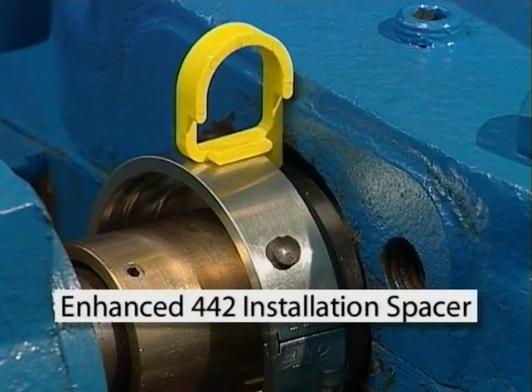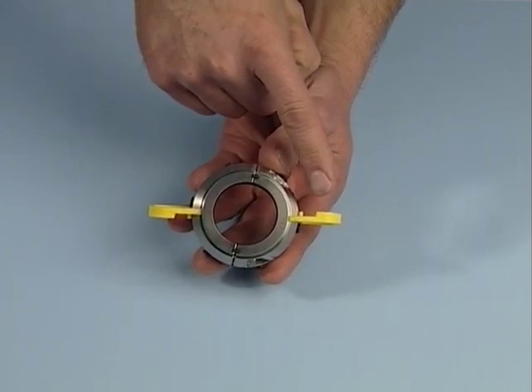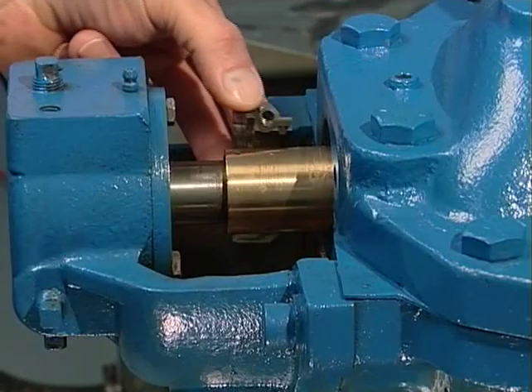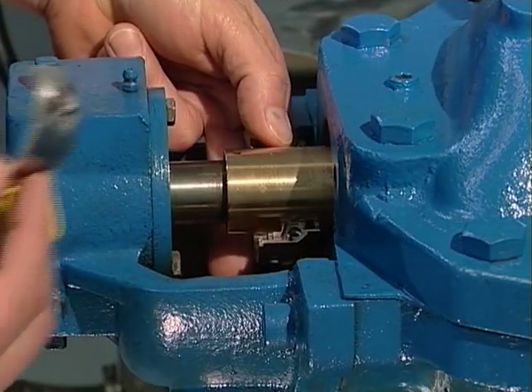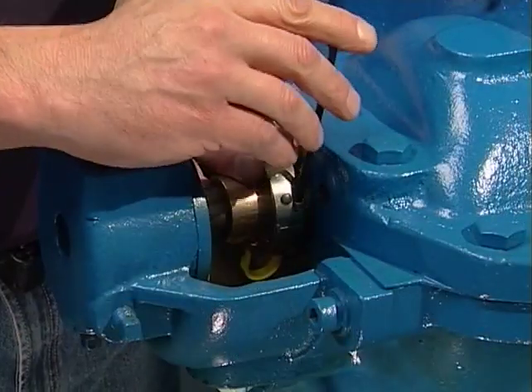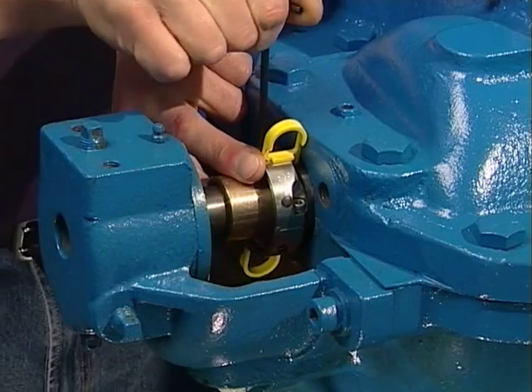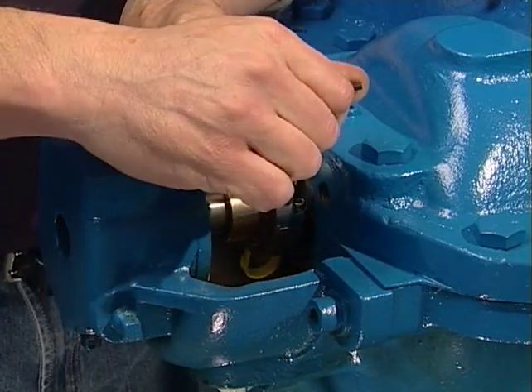Setting the enhanced 442 rotary holder with installation spacers attached. The enhanced version has two D-shaped spacers that are affixed to the holder halves. Place the rotary holder halves around the shaft. Tighten the two socket head cap screws while firmly pressing the back of the spacers against the stuffing box until tight on the shaft.